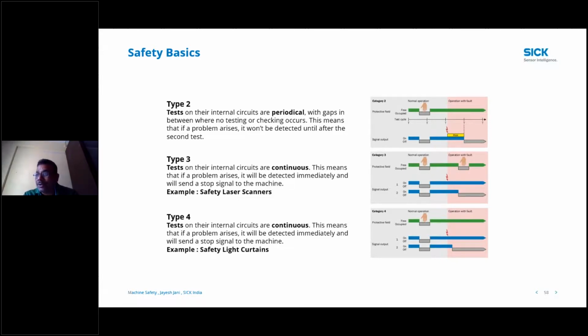But in type 3 and type 4 products, this internal check is a continuous process. During internal testing, if something goes wrong with the device itself, your safety is not affected - you will always get a safe output, and your machine will go into a fail-safe state. This is the advantage of type 3 and type 4: safety is always maintained even during internal testing, while in type 2, for a certain period of time the safety may not be available. So this is the basic difference.